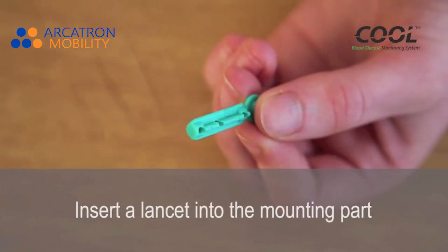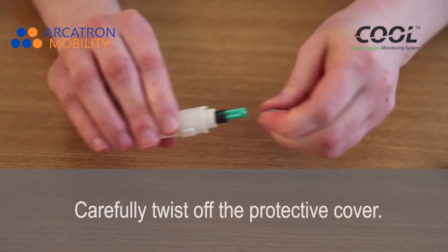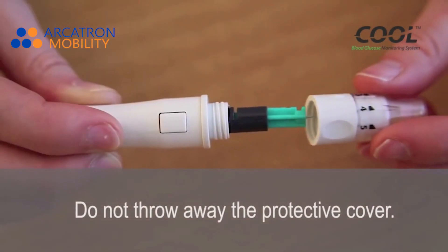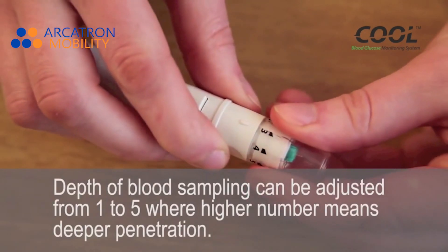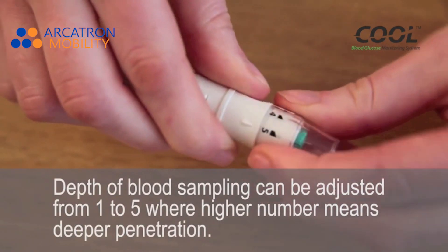Insert a lancet into the mounting part and push it all the way in. Carefully twist off the protective cover — do not throw away the protective cover. The depth of blood sampling can be adjusted from 1 to 5, where a higher number means deeper penetration.